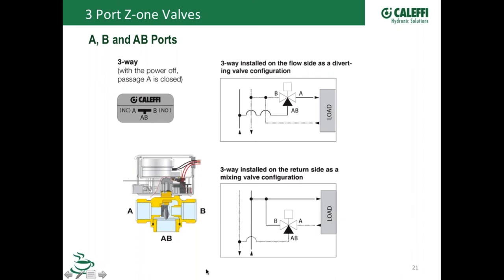So if you do have a large pump that you can't keep shutting off a zone valve against without running up the curve, that's the application for this three-way valve. And this is common on a lot of little fan coils or air handlers that get shipped out with a three-port valve like this, so they can have that bypass circuit around it. And then right here in this little parentheses up here, with the power off, passage A is closed.